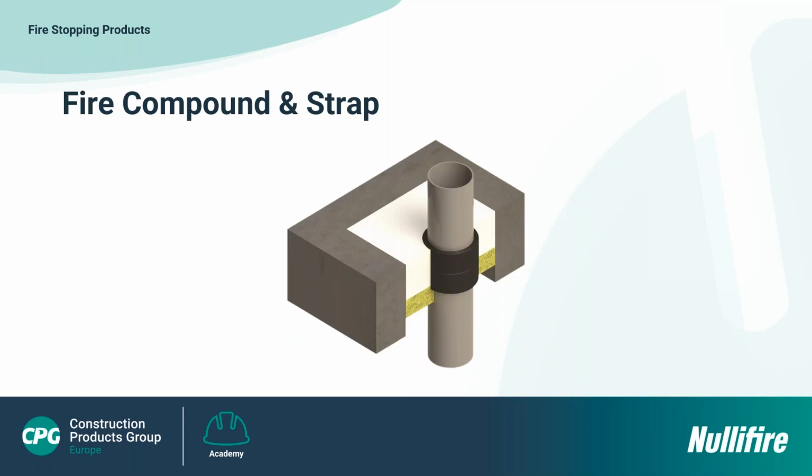Then you go on to things like the fire compound and using a strap within a floor. So mainly used in floors, can be used in some wall situations. It has got load bearing capacity. You install ours at 100 mil depth, and it's where you'd be getting expected footfall and that kind of thing. The strap, with the intumescent material within it, is used around the pipe. So it's using the compound to hold it, so that once the intumescent swells, it will go inwards to where the pipe was. It's not going to go outwards because it's pushing against the compound. So you've got your fire stop and allowing a load bearing element in there.